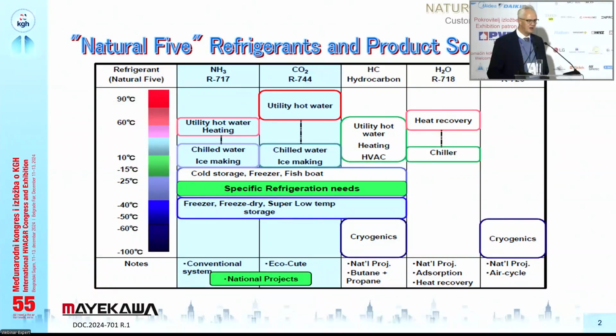The compressor is replaced by an adsorber and a desorber. And we use products like, for example, silica gel in the old time. And the last column is air, but it is not normal air compression as we have so many manufacturers available on the market. No, this is special air used as refrigerant, but below minus 50 degrees. And we are using a centrifugal compressor, oil-free, for that job. And it's mostly applied and used in the cryogenic industry. But it is totally natural. It's the best natural refrigerant, to say.